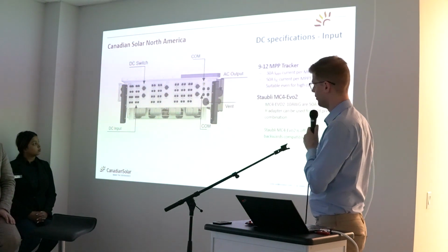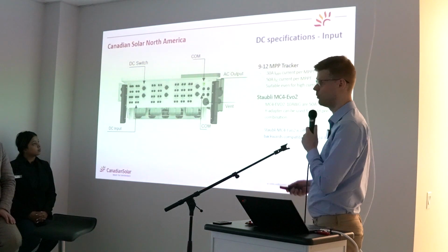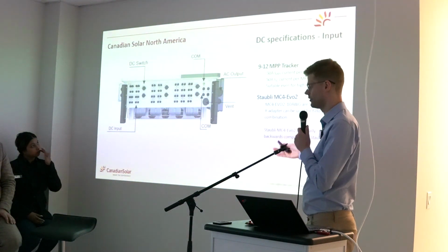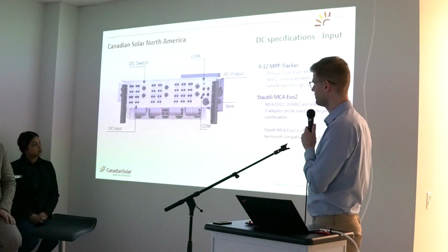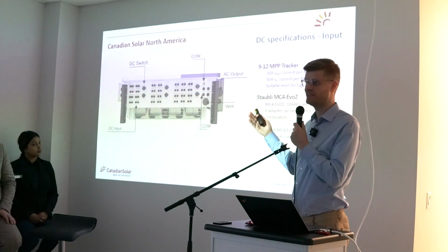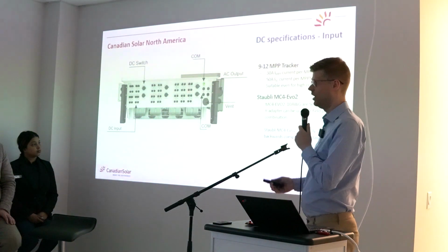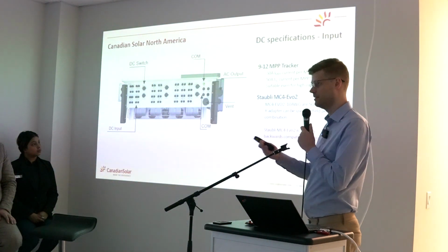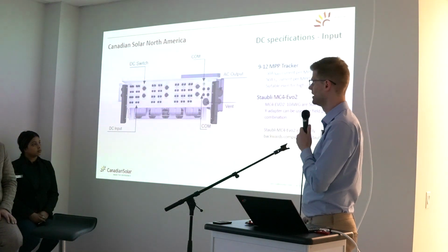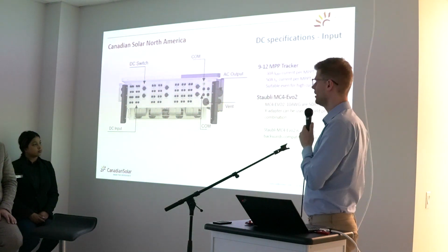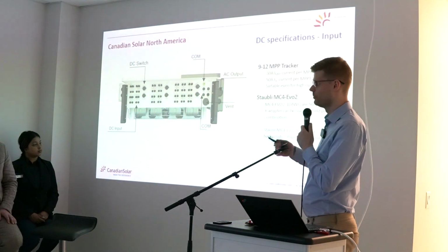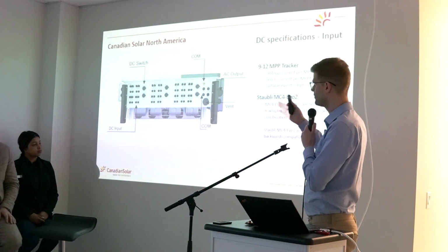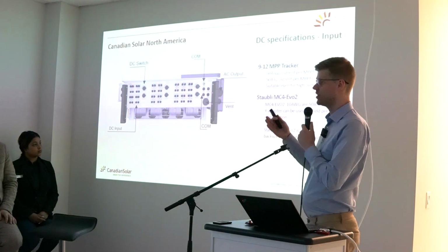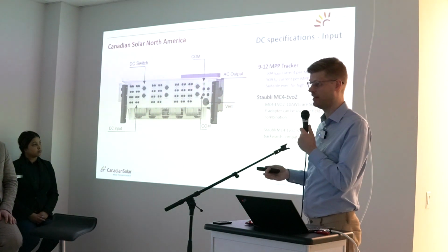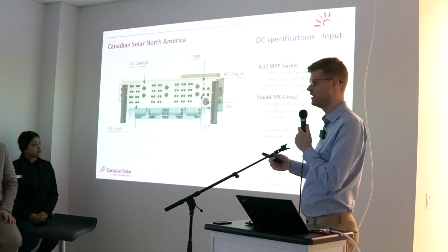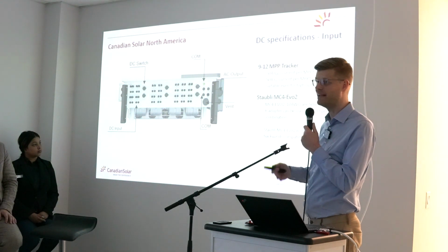Jumping right into the inverter, or to the bottom of the inverter, you see with these very large power classes, 100, 125, 185, and 255 kW, you have a large number of DC string inputs available to you. It's not a single MPP inverter anymore, like in the older days with the decentralized systems. It's typically now similar to a smaller C&I product, an inverter that has multiple strings directly landed. In this case, we have up to 12 MPP trackers. Each MPP tracker can have up to 2 strings in parallel, and that's a very, very good design philosophy because by code you can have 2 strings in parallel without any fusing requirements.